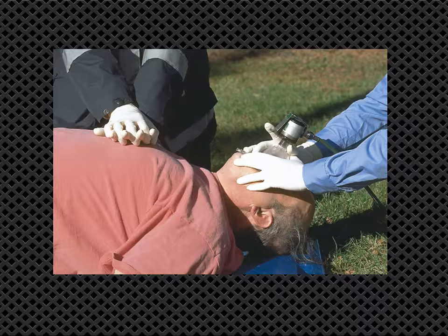We used to call this the demand valve. The problem with the demand valve of 20, 30 years ago is that there was no stopping the pressure. If we held that button down, we would just deliver a ton of volume into the lungs. The ones nowadays, at least in theory, have a flow restriction so that if you reach a certain volume, it's going to stop the flow so we don't blow the lung by putting too much volume in.